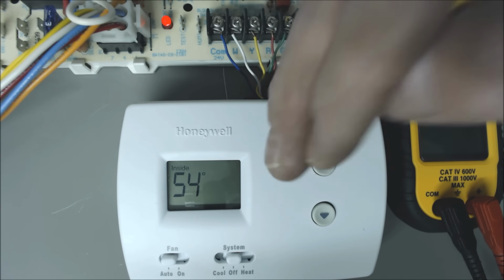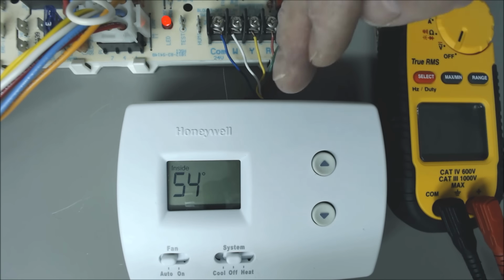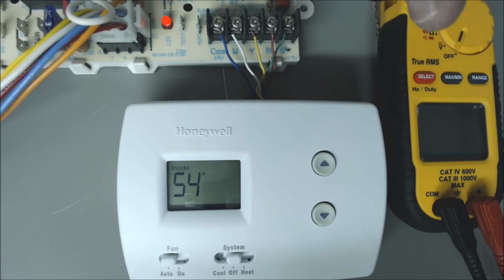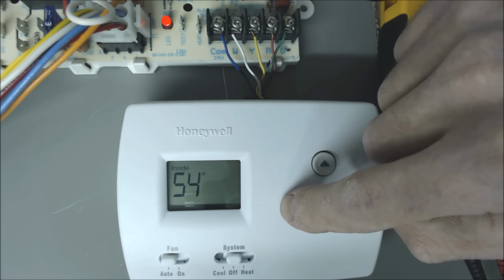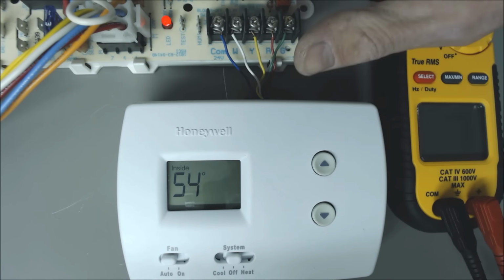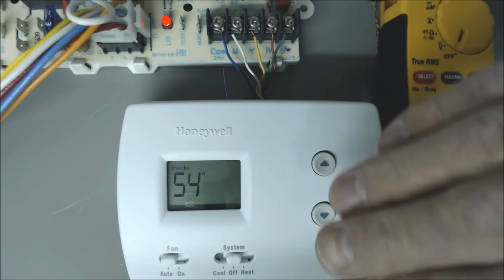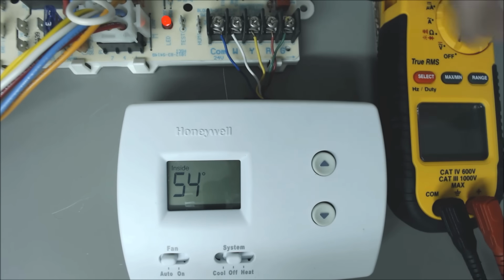Today we're going over how to read the voltages at the control board to verify that the thermostat's actually calling for either fan, heat, or cooling. I've been having a lot of questions come in, like, hey, I'm turning my thermostat on heat and nothing's happening, or I'm turning the thermostat on cooling and nothing's happening. So my first question always is, do you have 24 volts between the heat wire and common, or the fan wire and common, or the cooling wire and common? So in this video I just want to go over that.